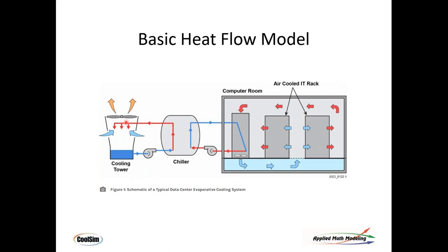These configurations can change quite a bit. For example, there could be a bypass plate-and-frame heat exchanger around the chiller so that on certain days you use economizer mode — just going through the cooling tower because it's cold enough outside that you don't need compression. When modeling these things in a transient case, you need to know all that — what's going on outside — in order to define the problem correctly.